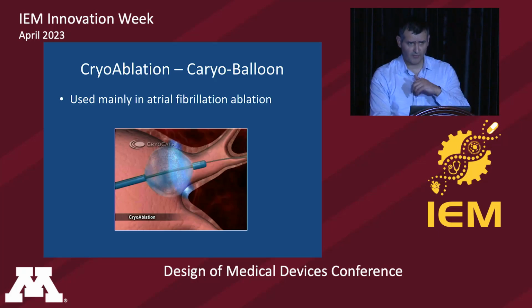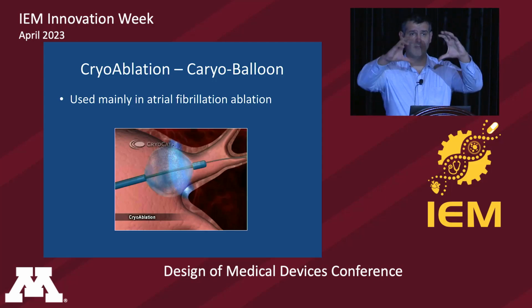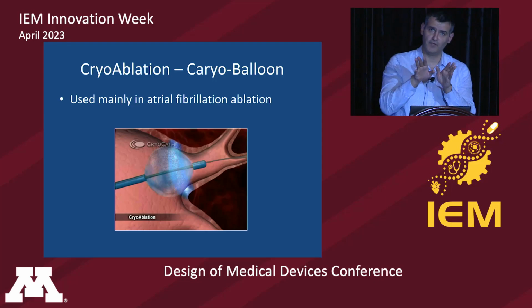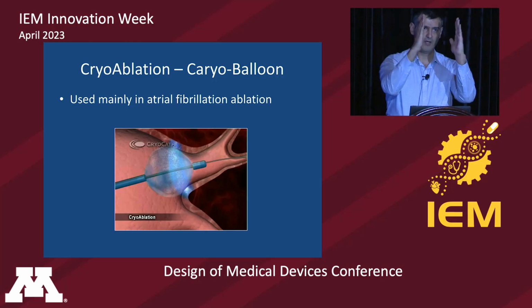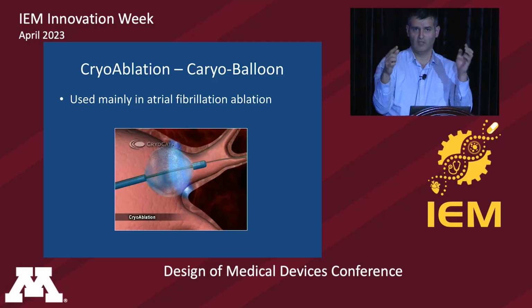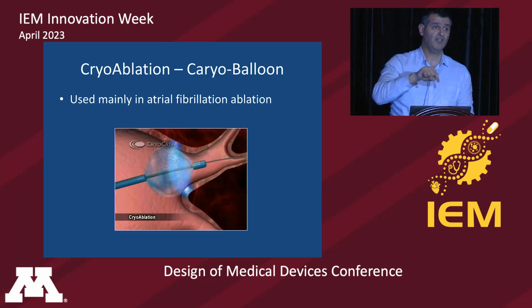So there is a new version of it. So there's a cryocatheter, which is just a catheter tip. The cryoballoon is instead a balloon that the refrigerant gets injected in a fan at about 30 degrees to the front, not right in the equator of it. It's a bit to the front of it, where it creates a circle of freezing, basically.